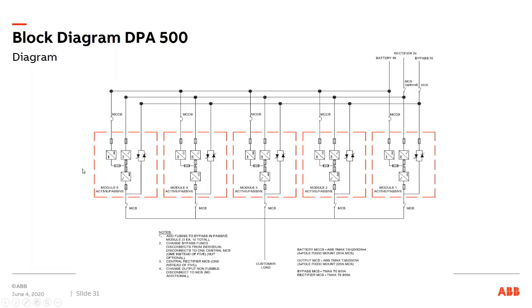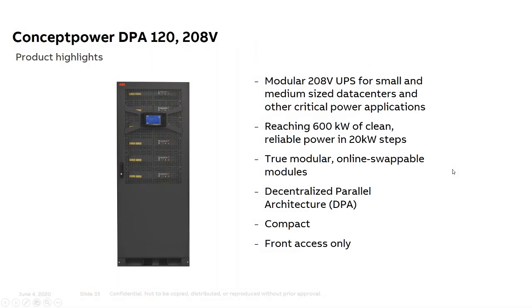The benefit with the ABB modular UPSs is that the power modules are complete UPSs. So they operate like complete UPSs in parallel. There are no shared active components involved in controlling the operation. Every single one of the little UPSs here can control the entire operation of the system. So as I mentioned before, if the load is supported by one less than the power modules installed, like in this case up to 400 kW, this unit will offer a true N+1 redundancy in a single frame. And obviously, as more power is needed, it's possible to parallel this UPS as well to support higher loads.